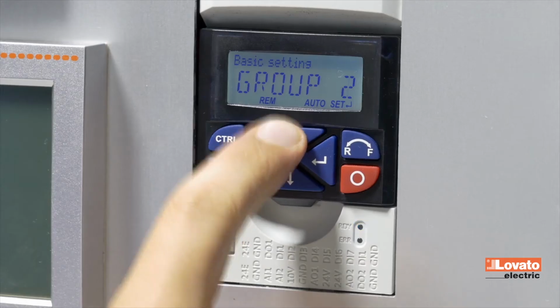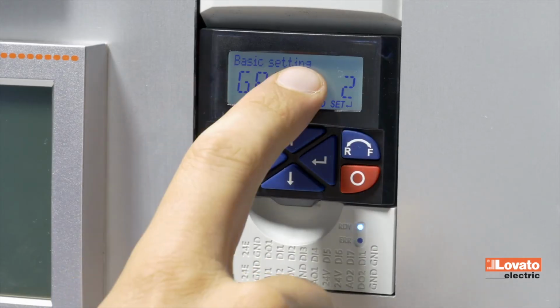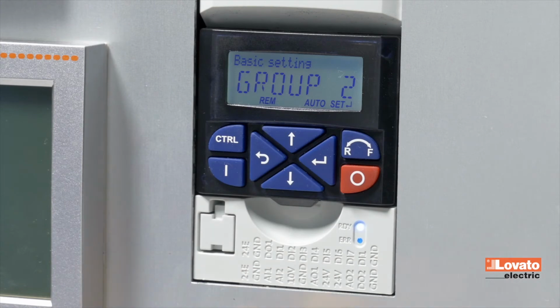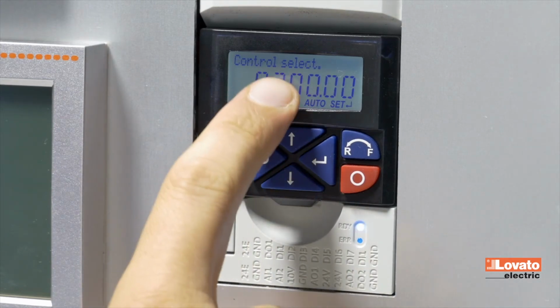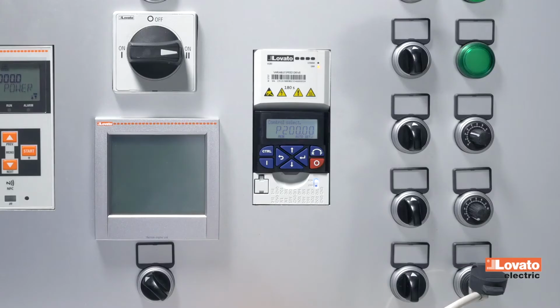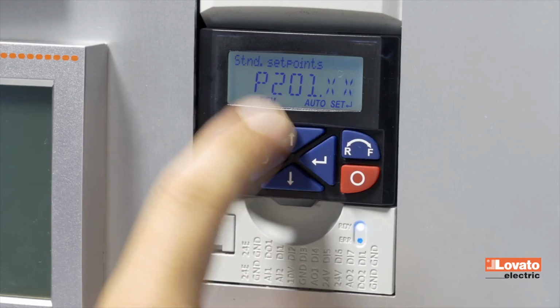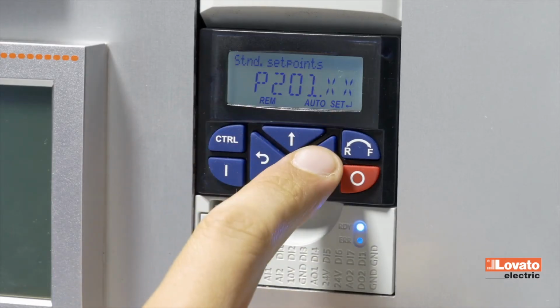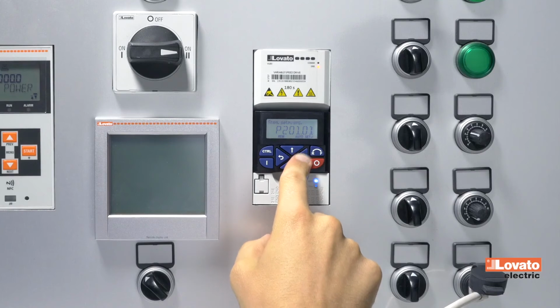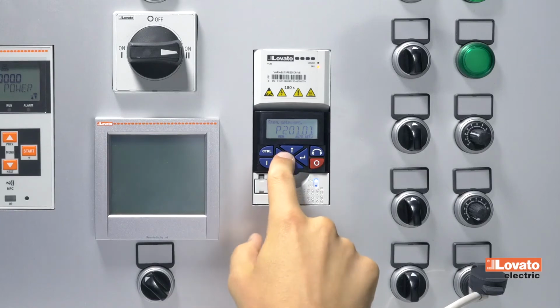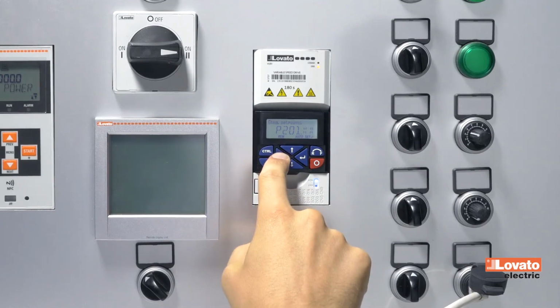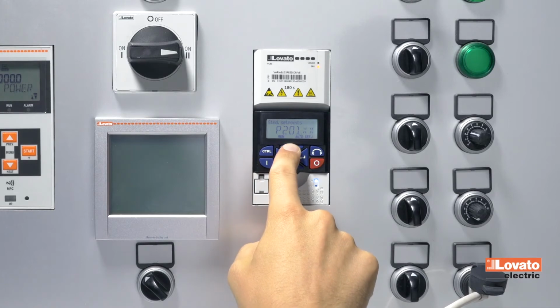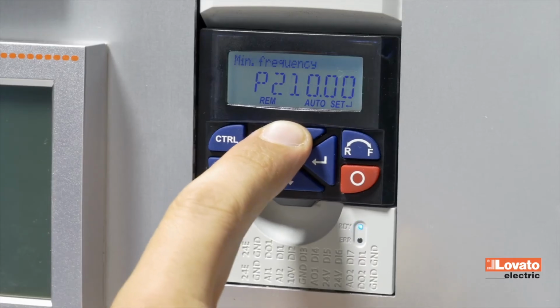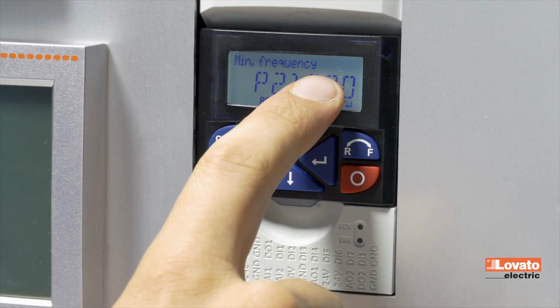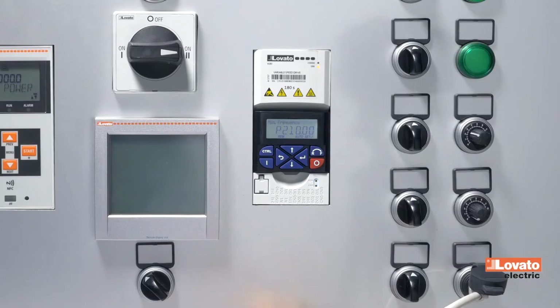Group 2 is one of the most important because it contains the main functions for programming the drive. The source of the start-stop command, the onboard keypad or the contacts on the terminal board, and is used to define the frequency control source, again from the keyboard or from the analog input and others. It is also used to program the operating limits, such as maximum and minimum frequency, acceleration and deceleration time, and so on.